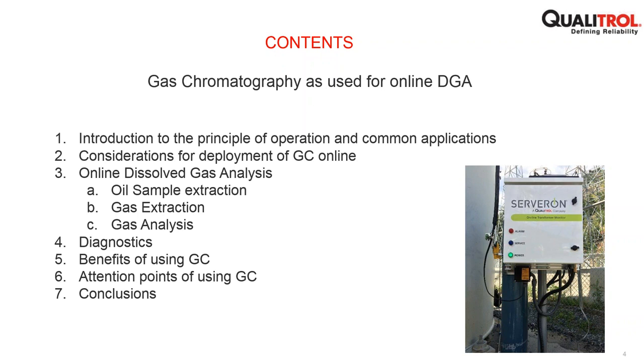On the right-hand side, the photograph is of a Serveron dissolved gas analyzer. This is an online system situated beside the transformer, collecting oil samples and performing dissolved gas analysis on a scheduled basis. I should say there are other systems out there other than the Serveron one, but Serveron were first to market with gas chromatography for dissolved gas analysis.